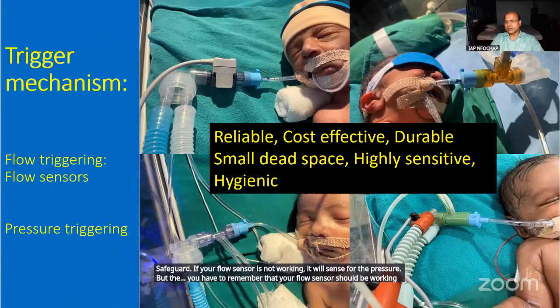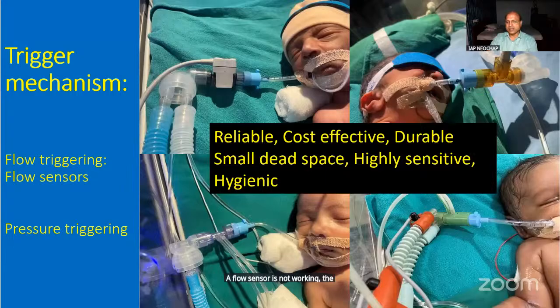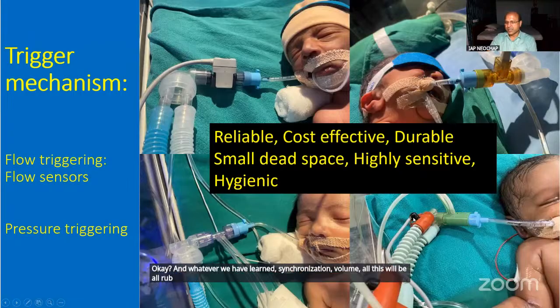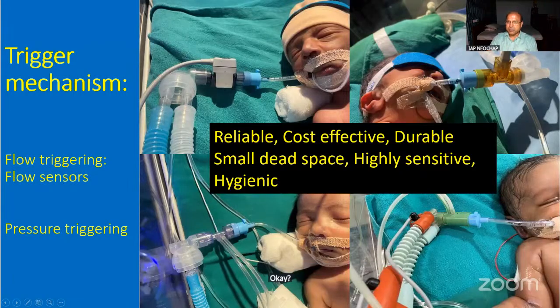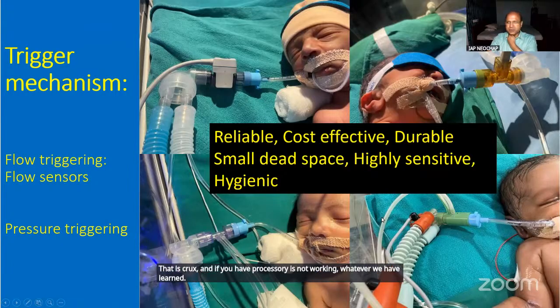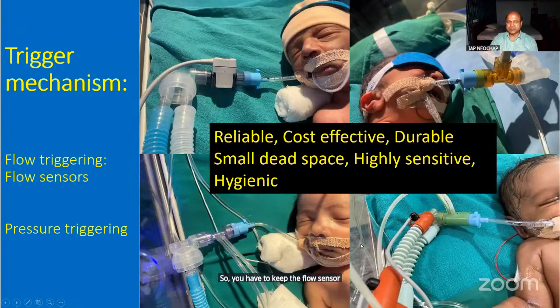If the flow sensor is not working, the ventilator is giving IMV, intermittent mandatory ventilation. Okay, and whatever we have learned, synchronization, volume, all this will be rubbish. So you have to make sure that your flow sensor is working. That is the crux. If the flow sensor is not working, whatever we have learned from the textbook, whatever workshop you are attending, all are useless. So you have to keep the flow sensor working.